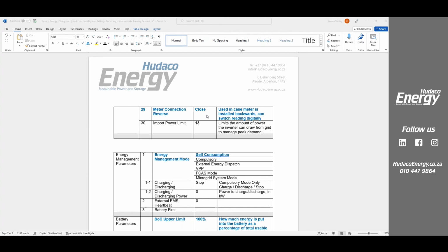The easiest way to tell if you've reversed the meter is your PV production and your load production will match exactly. You will not on the app see your battery and your backup load feed. You will only see a load and a PV line, and they will match exactly. You will not see battery and you will not see grid. The moment you see that, it's an indication, oh, I've installed my meter backwards. Just change this meter reverse connection and you'll see all 4 units come live again. And I'll show you what those look like in a moment.